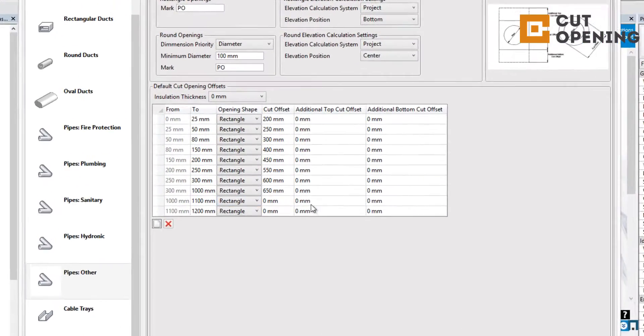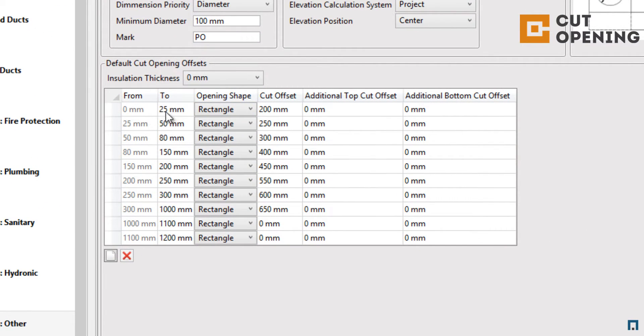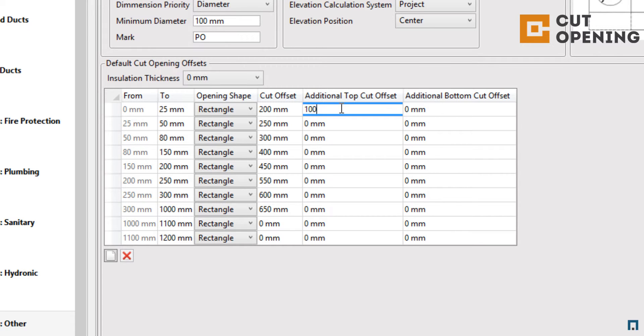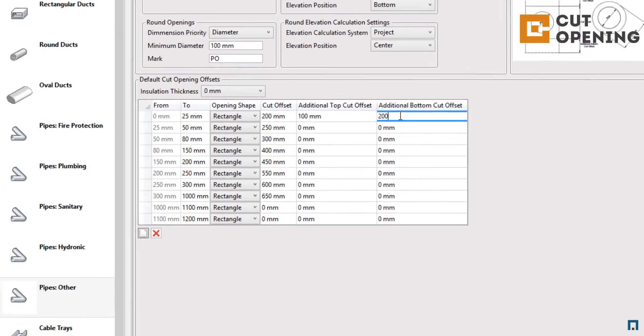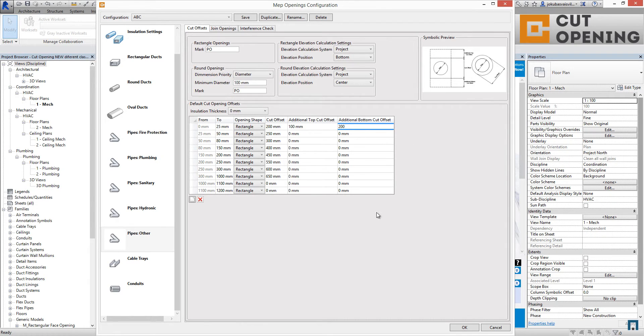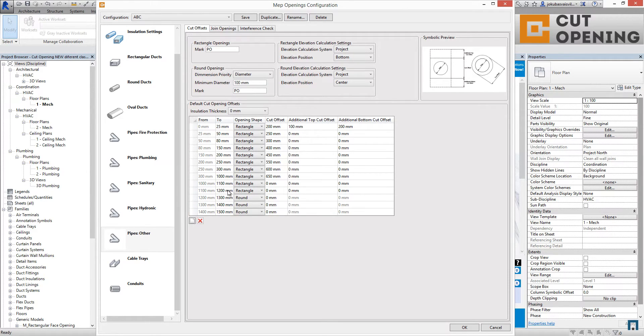We also have default cut opening offsets. There are different size ranges — for example, from 0 to 25 or from 25 to 50 — and you can set different opening shapes for each range, choosing from bottom, rectangular, or round. You can set different cut offsets, additional top offsets, and additional bottom offsets for each range. If you need new ranges, click the new button to create them. You can also apply the same settings for different insulation thicknesses for pipes or ducts.